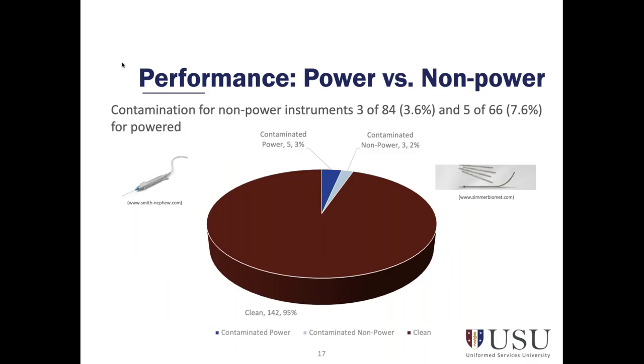Now, the contamination rate for power instruments, 5 of 66, as I already mentioned, was a top concern because this type of instrument cannot sustain mechanical cleaning and is packaged for sterilization right after manual cleaning. A recent quality improvement project performed by myself last year at a large medical center documented the importance of mechanical cleaning and how it can significantly lower the chances of bioburden retention. In this project, a total of 14 out of 59 manually cleaned instruments tested for ATP failed. The failure rate after mechanical cleaning was significantly lower when compared to manual cleaning. Only 2 out of 59 instruments failed ATP testing after mechanical cleaning.